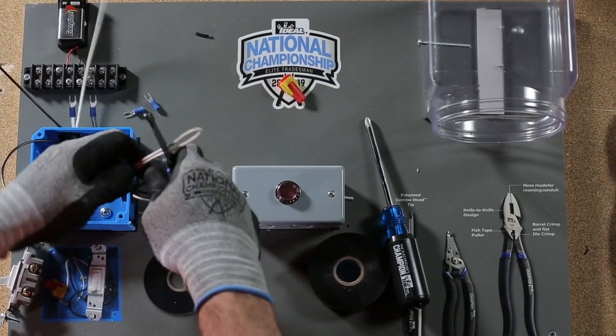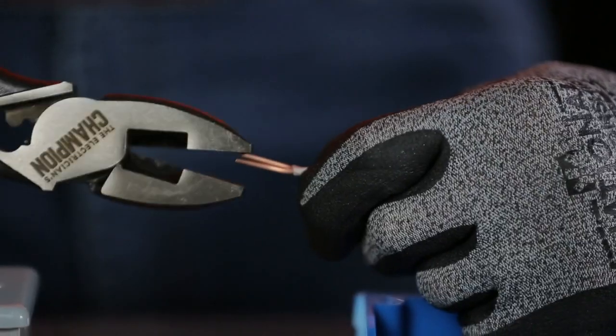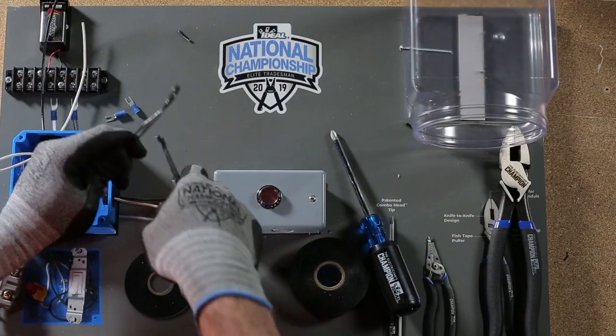In the electrical box, cut both wires and strip all ends with the T-Strippers. Using the Linesman pliers, pre-twist the white conductors and terminate with the Ideal Twister Pro wire connector.